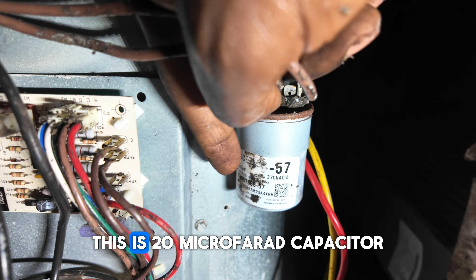Now what I'm going to explain is the wiring, and why we call this a direct drive motor. A direct drive motor is just a motor that starts running when power gets into it. It's not an ECM, electronically controlled motor. When it receives 240, it starts running, depending on the speed you wire it. These wires correspond to different speeds, but they use this one, which I believe is for the highest speed. Now, let's look at the wiring configuration of this motor.